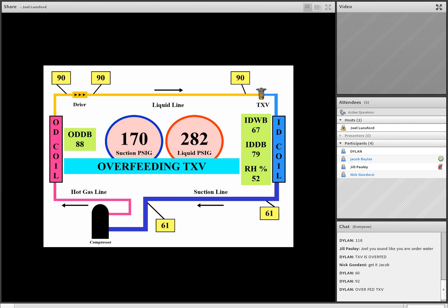Now, team, maybe make a note of this from a field standpoint, a little field tip. A lot of times an expansion valve will overfeed, especially if it's been in service for a while. If it's on initial install, they may have damaged it when they installed it by overheating the sensing bulb. That'll cause them to overfeed. But if it's been in service for a while, sometimes that sensing bulb will get some corrosion under it, on the sensing bulb where it clamps onto the suction line.